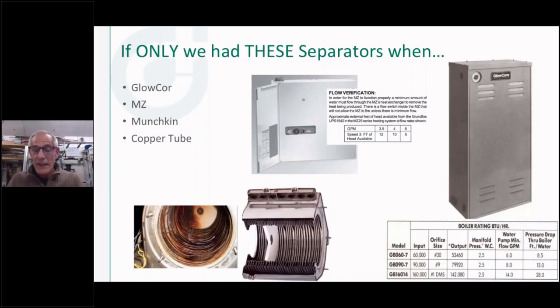So back in the day, some of you folks online might remember these days, some of these boilers of years gone by: the GlowCor up there on the upper right, the little MZ Monitor there in the center, and of course, we're still using heat exchangers like you see on the lower left. Common to all these is they're a pretty high pressure drop type of heat exchanger in this boiler, so they take a bunch of pumping power. In the table on the GlowCor over here, you can see how much pump and what kind of pressure drop there was through that boiler. You can see the different sizes and the flow rates and the pressure drop through that boiler.